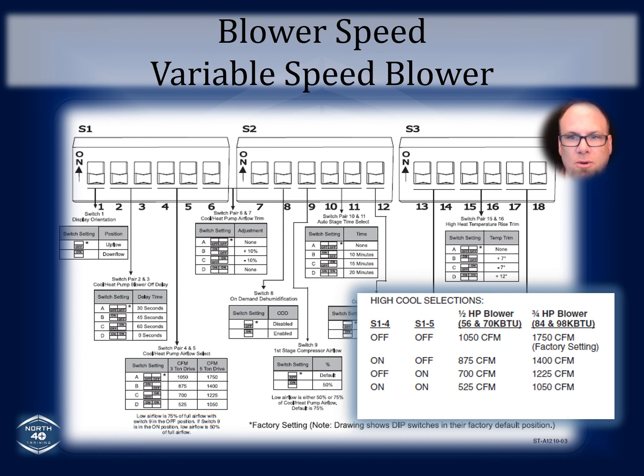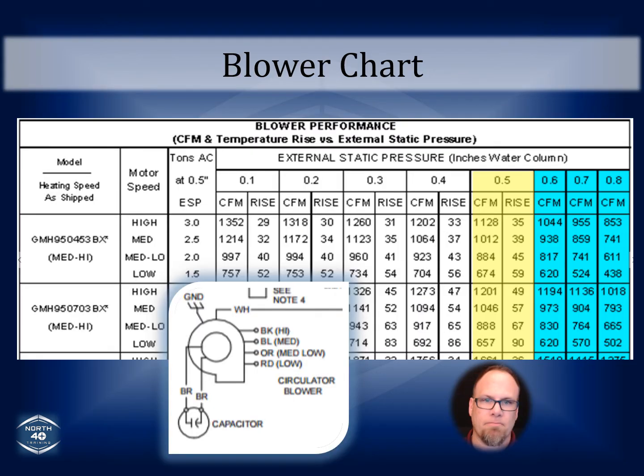In doing so, the amp draw goes through the roof. So you've got a motor that's extremely efficient as long as it's in the application that it was designed for, which is 1 inch of static or less, and according to manufacturer specs, 0.5 inches of static or less. If you put it in that application, it will run much more efficiently than its counterpart in multi-speed blowers. Again, here's your blower chart.